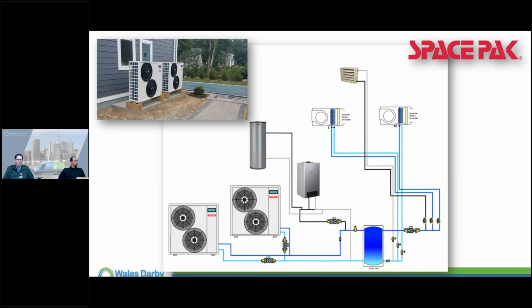Quick question about placement of the outdoor unit, regardless if it's a DX, meaning just straight refrigerant, or air to water. These things are on rooftops. Is there better performance on the north side, south side, shaded, not shaded? I'm not really sure performance-wise where they test it for those numbers, but it is an air source regardless. You get them off the ground, make sure you're protecting them from snow loads, flooding, things of that nature.